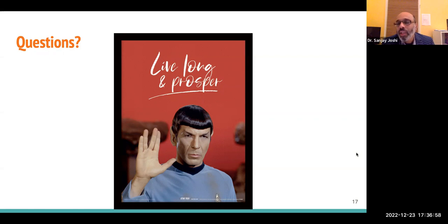And as you said, if there is that 1% or this outlier that we never thought about during design, but it did happen, then again the question you ask is, are there existing controls? Number one, are they there? Number two, did they work, and did they work effectively to eliminate harm from the patient? If they did, you are okay. You need to write down all these things. If they did not, and you have to change the design of the product, or alert the user that such and such unsafe situation can happen, that would be a safety recall on the product.